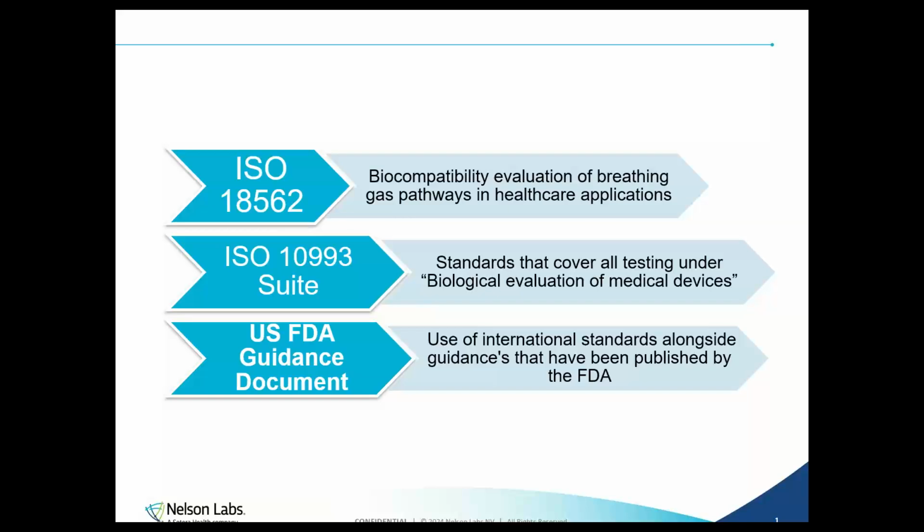However, there's been a little bit of a split in these overarching documents because of special externally communicating devices, such as those that carry air or gas to the lungs. When a gas is the carrier of the externally communicating device, the risk profile is a little different than if the carrier was a liquid, which is the suggested matrices of the ISO 10993 series. From a toxicological standpoint, more often than not, these gases can be more toxic, more problematic, and in some cases, they can result in unsafe exposure to chemicals that come off of medical devices.